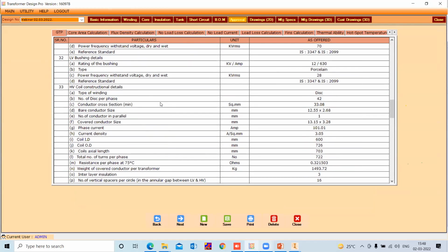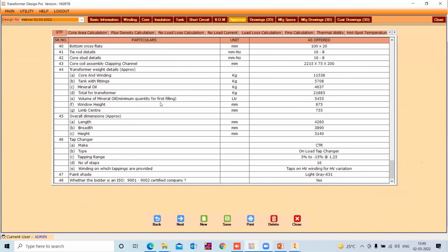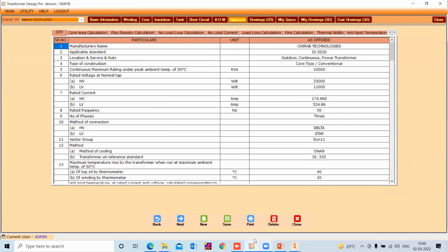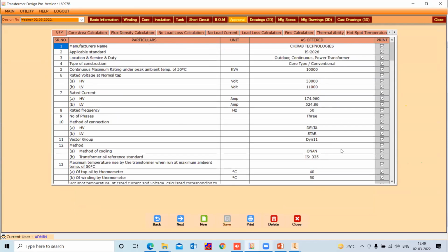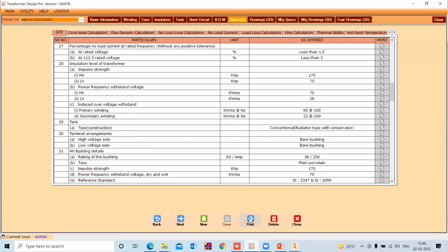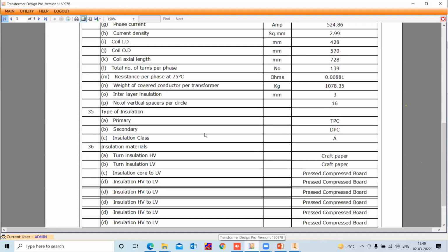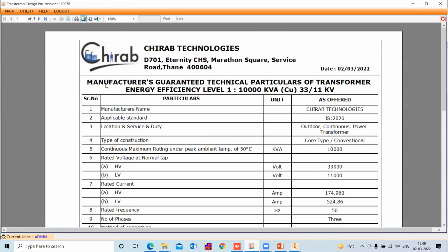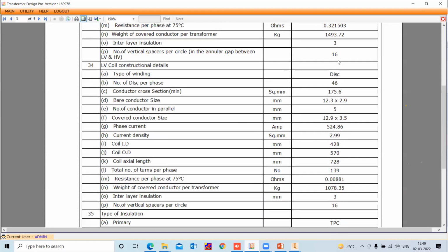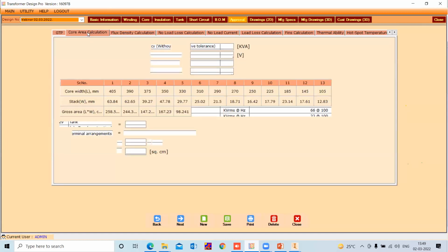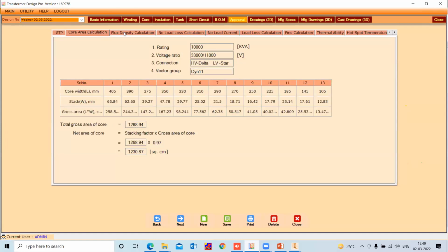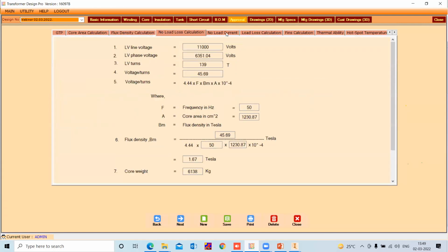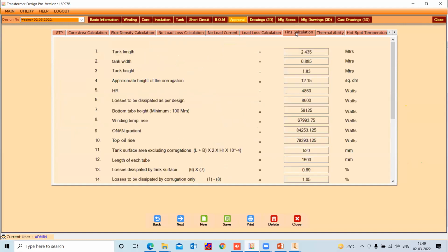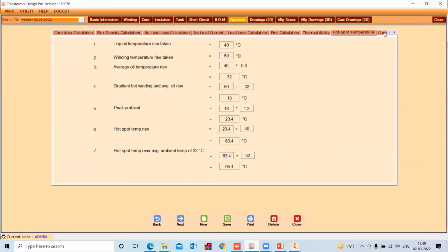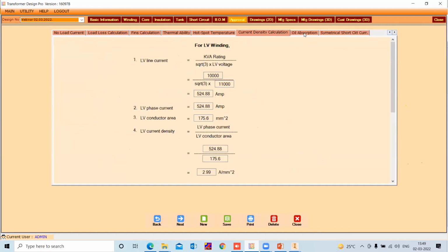So 5 pages of GTP are generated for this 10 MVA also. And again, the option is available to remove some item from this GTP. And based on that, your serial number also will get rearranged. You can see the 10 MVA copper 33/11, all information. Customer logo and company name is available to edit. Core area calculation, flux density calculation, thereafter the no load loss calculation, no load current calculation, load loss calculation, fins calculation, thermal ability calculation, hotspot temperature. These all calculations are available for all types of transformers.